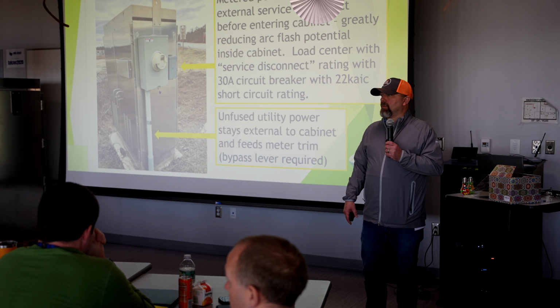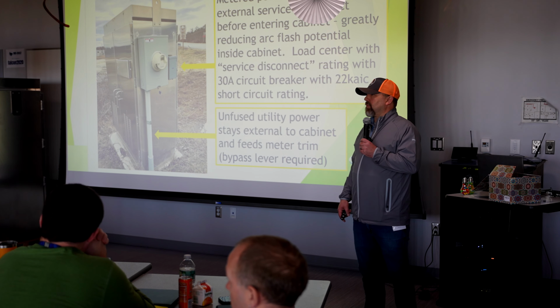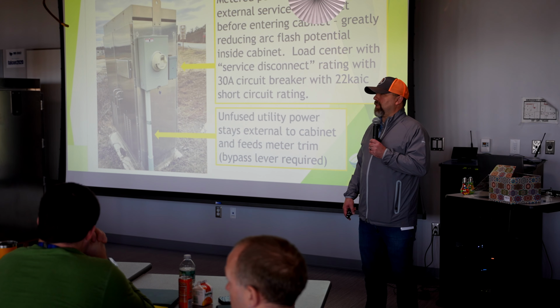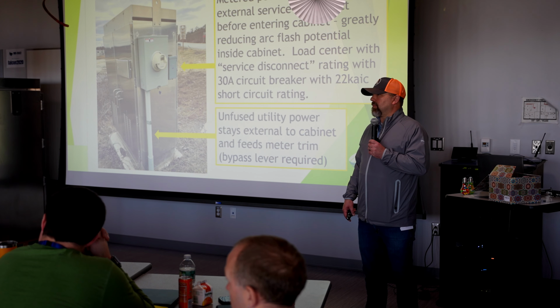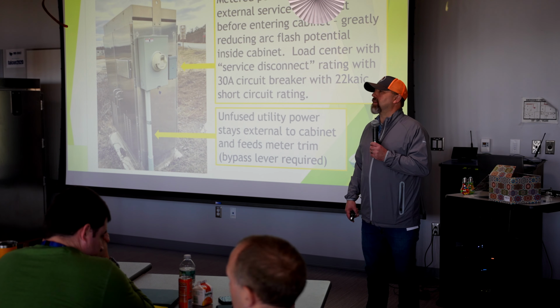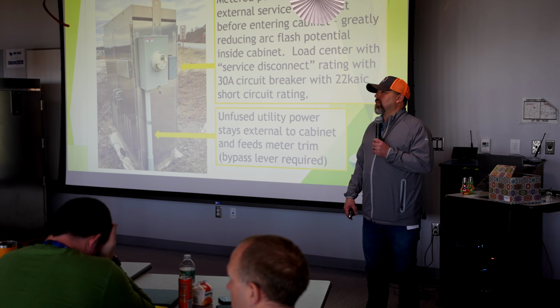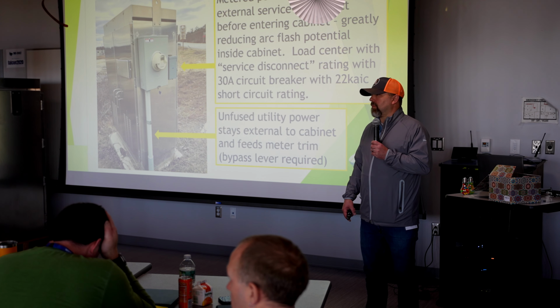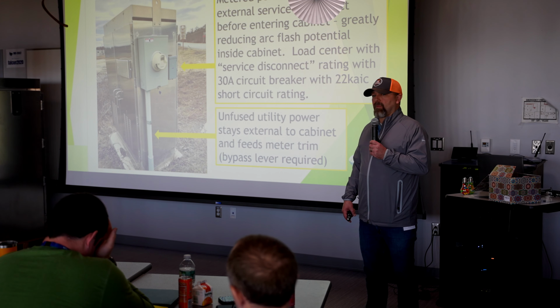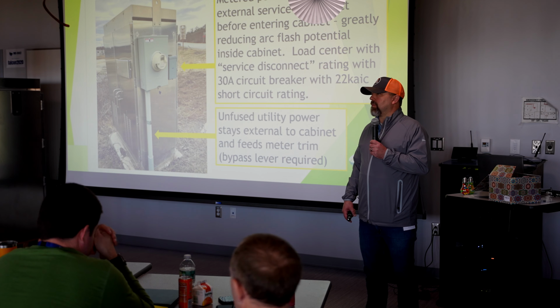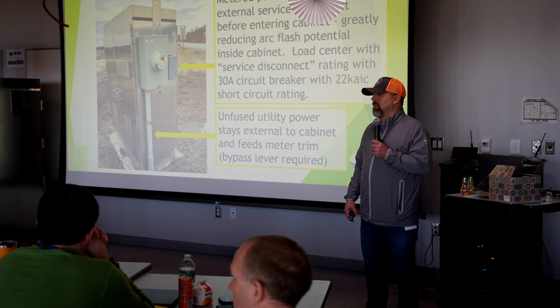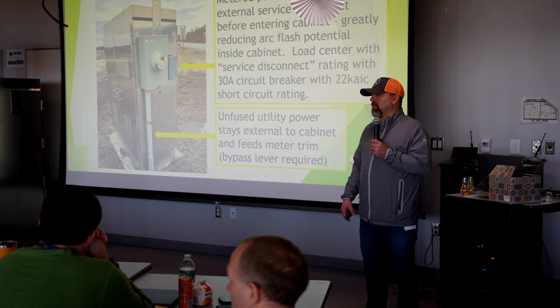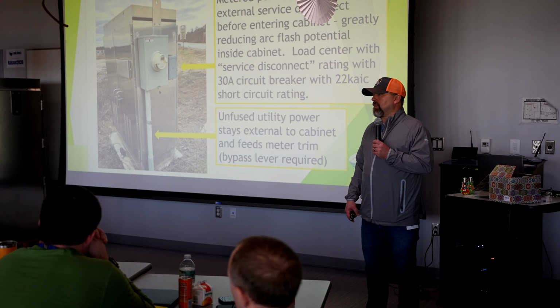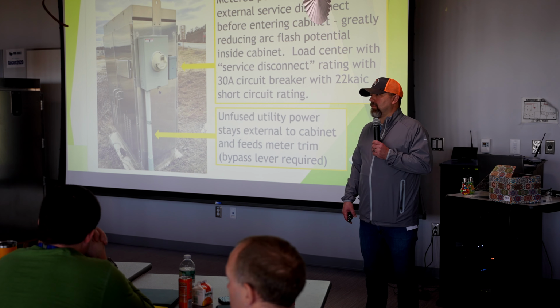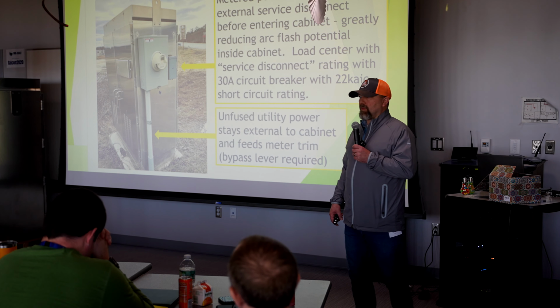Even on our street lighting cabinets in Portland now, we're not doing them on our street light services. We're doing them on small EPX enclosures, 18 by 18, about 4 to 6 feet high, high enough to get the meter on. The meter enclosure has to be 36 or 42 inches, so we use metal cabinets there too, because they get hit by plow trucks and cars. Those are more forgiving. They'll dent it, but they hold up better than a 4x4 or 6x6 post. We've gone to that pretty much standardly for the city.